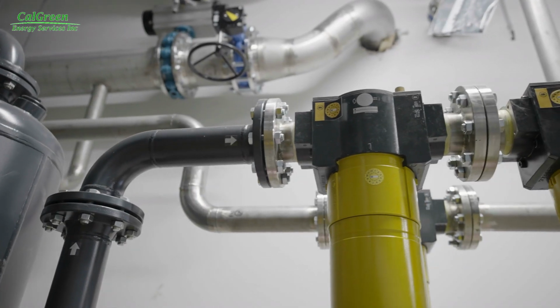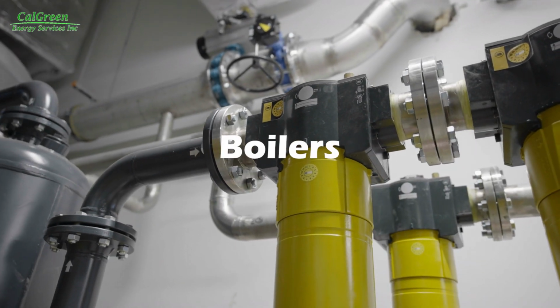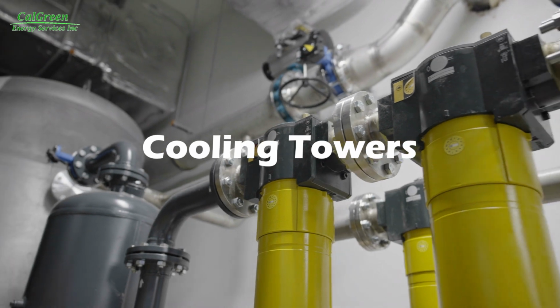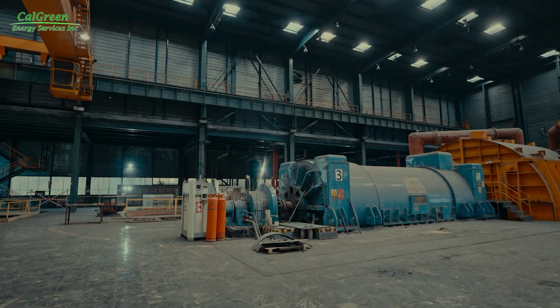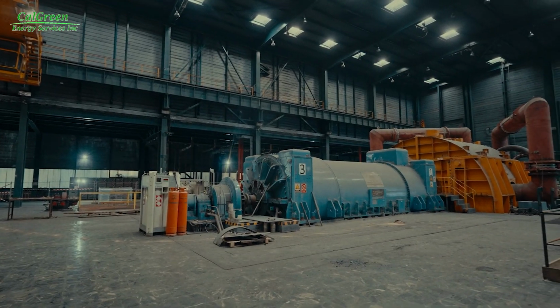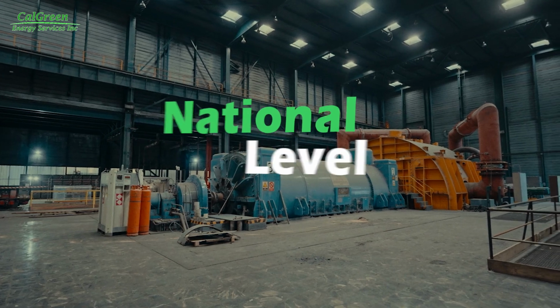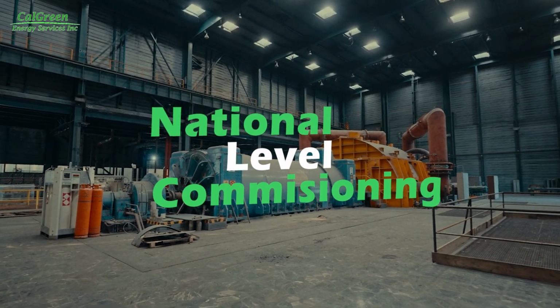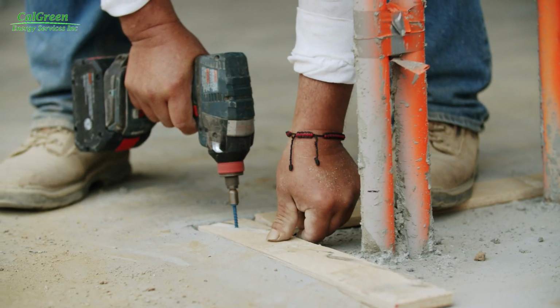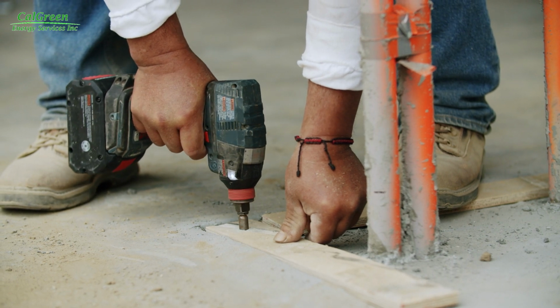For example, if your project includes boilers, chillers, cooling towers, emergency generators, and a complex energy management system, national-level commissioning might be worth it. But for less complex systems, the added cost often provides little benefit.